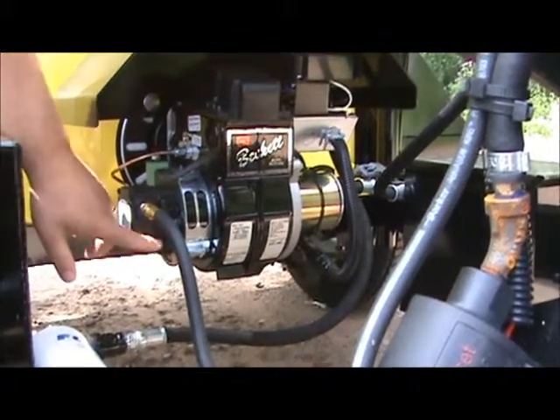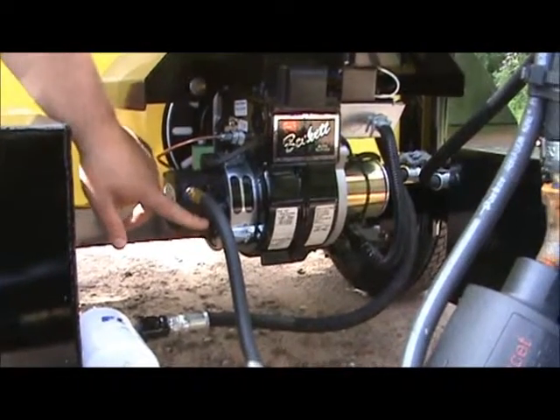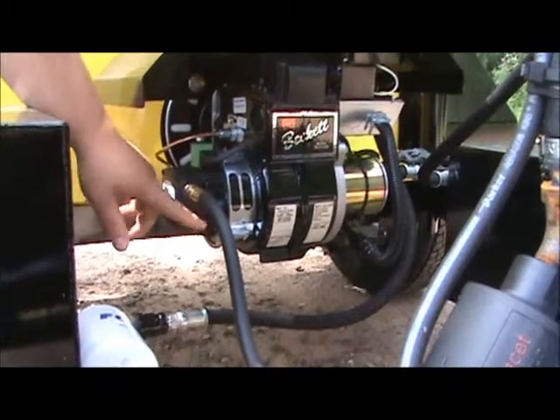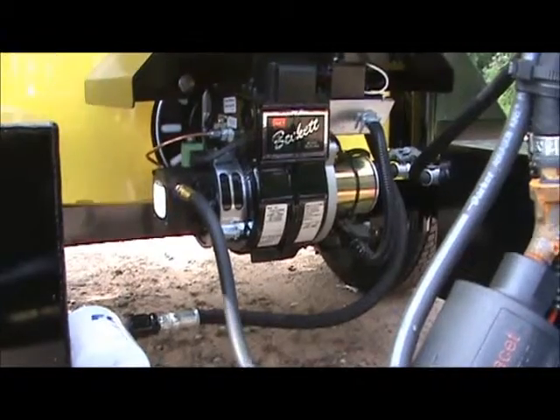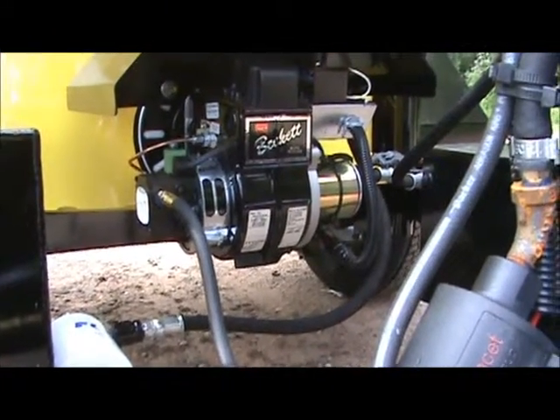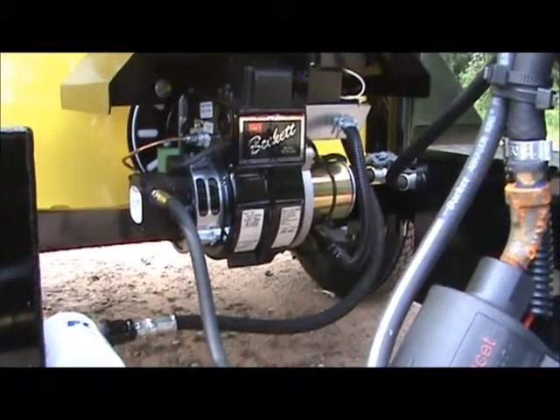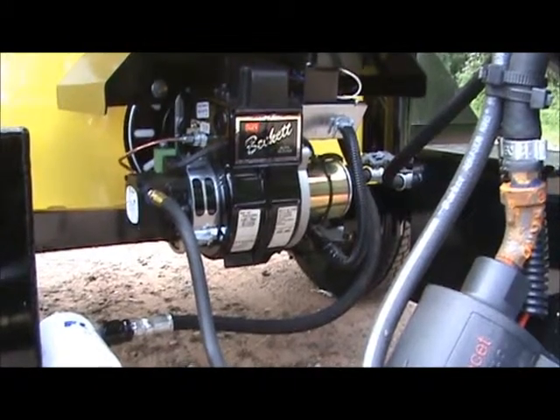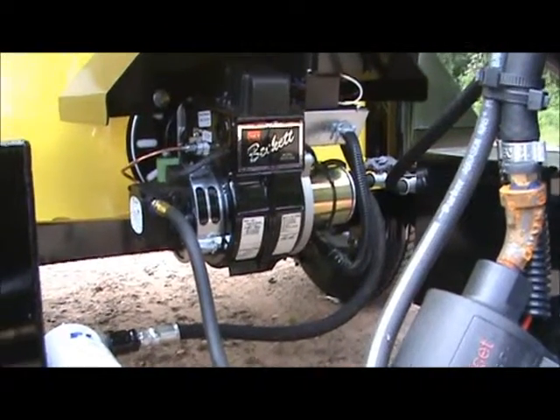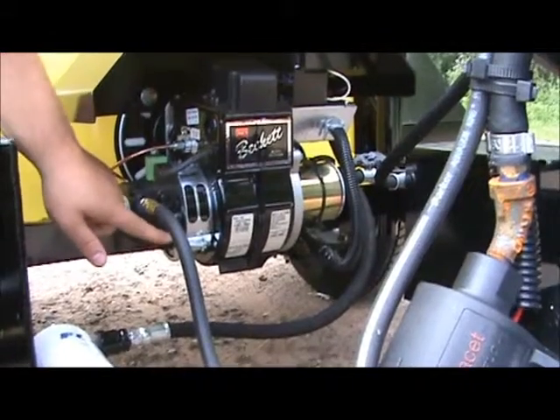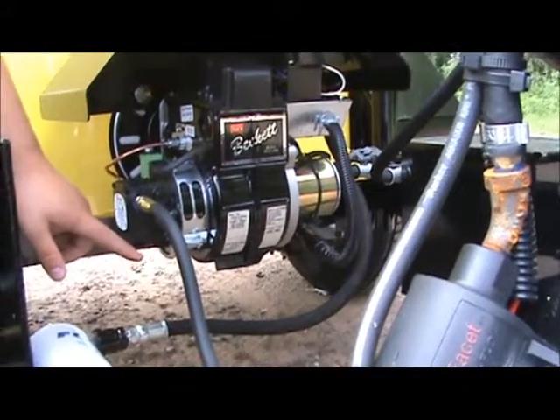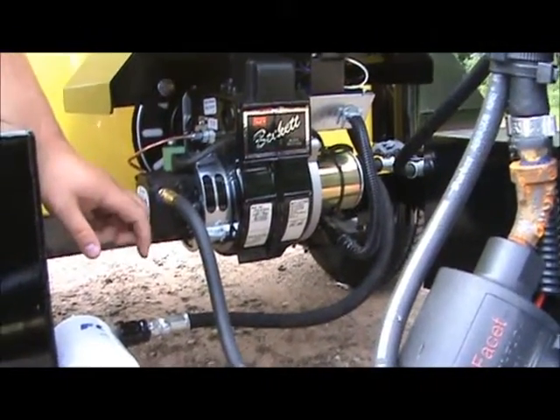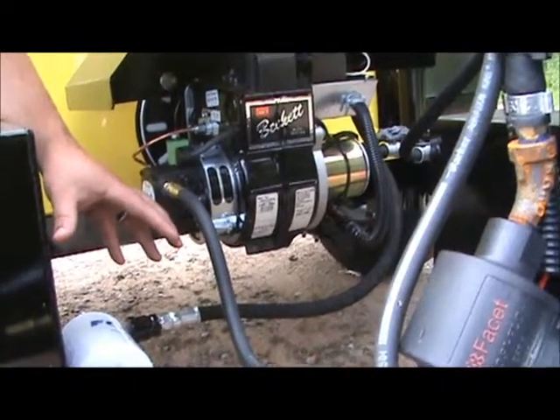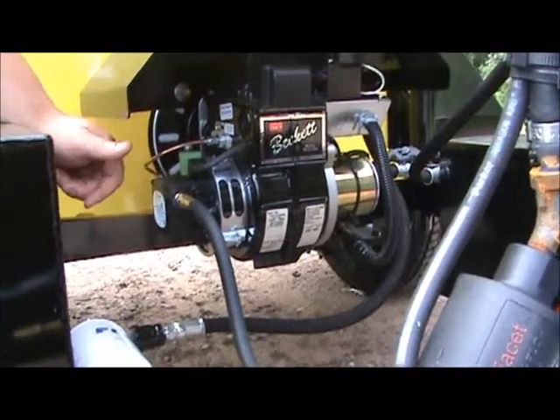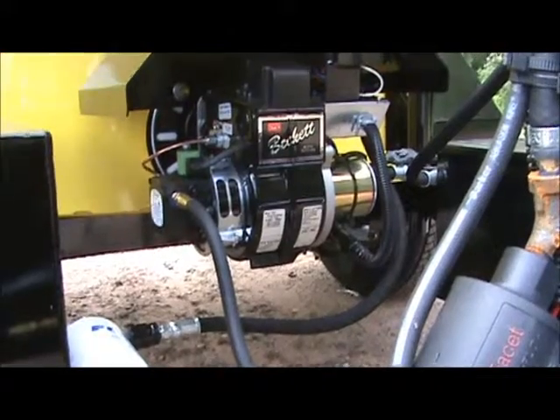Now on the bottom side of the burner, to check to see if we have fuel, there's a petcock. We can open that up and it's going to spit and sputter fuel out. Now if it's spitting and sputtering, it means we've got air trapped in the system. So we have to get that air out. So you have to bleed the burner. If you ever run it out of fuel, that's what you'll have to do. You'll have to open the petcock, turn the switch on, and you may have to cycle it 2 or 3 times until you get a good steady stream of fuel out of there. And then usually you close the petcock and the burner takes right off.